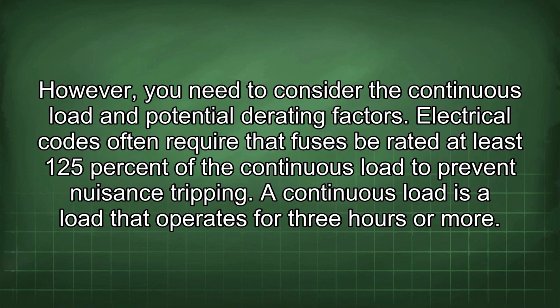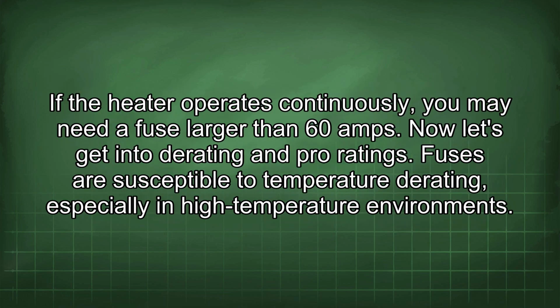However, you need to consider the continuous load and potential derating factors. Electrical codes often require that fuses be rated at least 125% of the continuous load to prevent nuisance tripping. A continuous load is a load that operates for 3 hours or more. If the heater operates continuously, you may need a fuse larger than 60 amps.